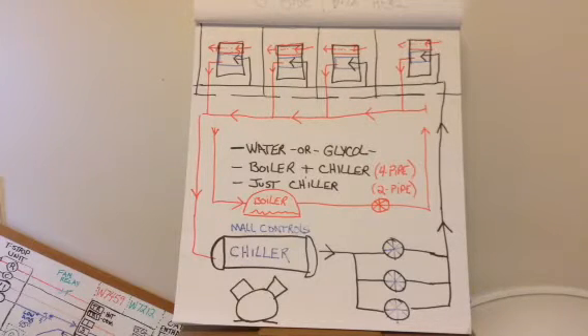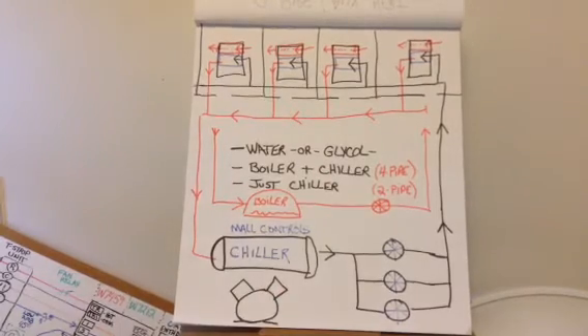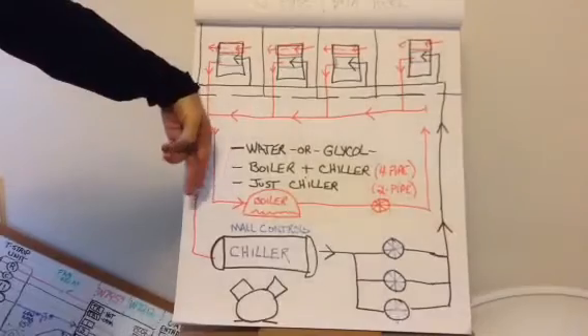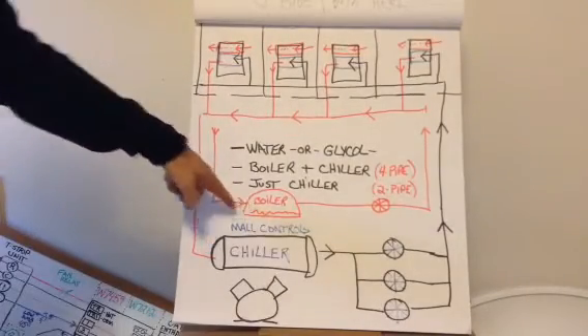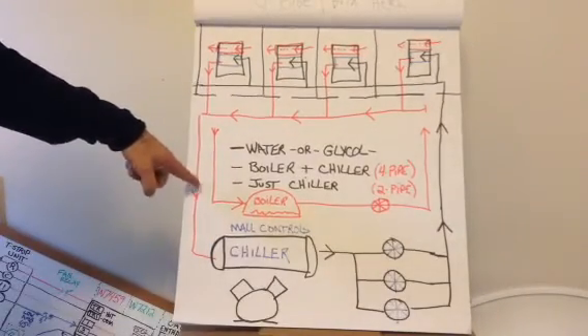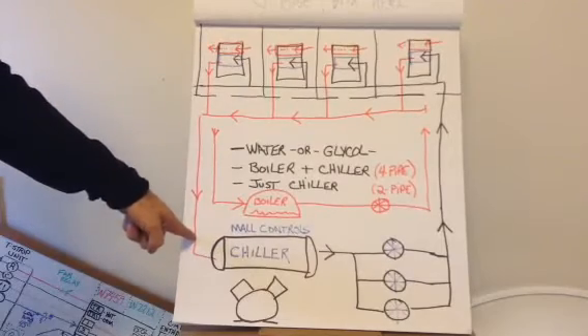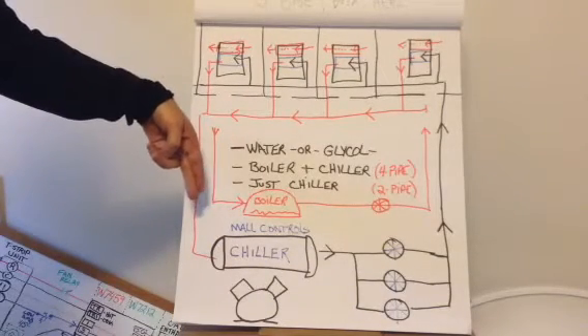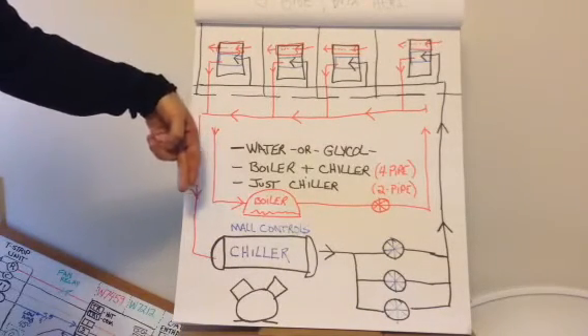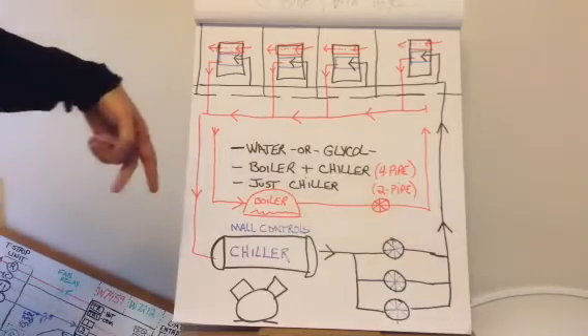Again, it depends on the mall. Some malls have two pipes, one supply, one return, but down in the plant, they tie these two together with valving, and in the winter, they heat the water in this loop. In the summer, they chill the water in this loop. So it's a two-pipe, but it's hot water in the winter and chilled water in the summer.